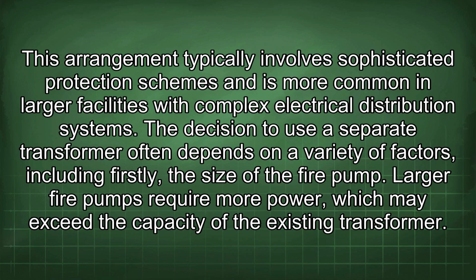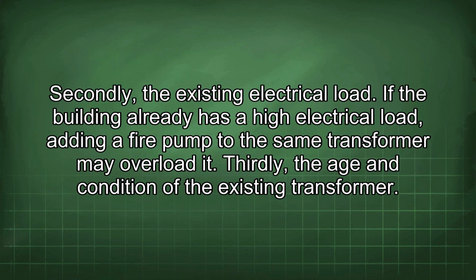The decision to use a separate transformer often depends on a variety of factors, including, firstly, the size of the fire pump. Larger fire pumps require more power, which may exceed the capacity of the existing transformer. Secondly, the existing electrical load. If the building already has a high electrical load, adding a fire pump to the same transformer may overload it.